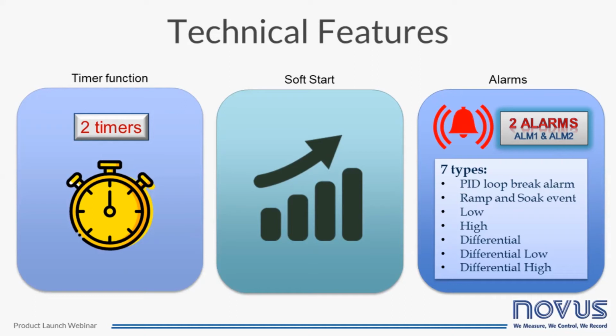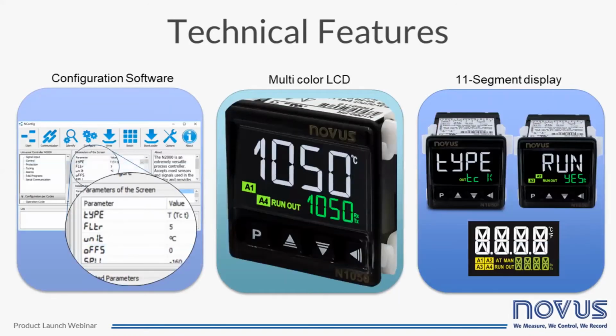The soft start function actuates on the output MV signal. When configured, it limits the control output rising rates, avoiding, for example, switching the output directly to 100%. It defines a time interval in seconds for the rising ramp up to the full output. For N1050 configuration, the N1050 software is available, which is a free configuration software that allows you to easily modify all parameters of the controller.